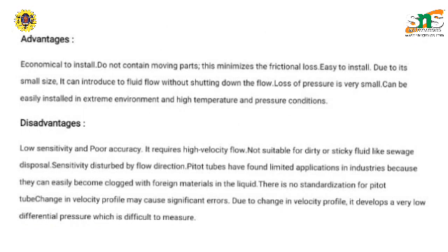Pitot tubes have found limited applications in industries because they can easily become clogged with foreign materials in the liquid. There is no standardization for Pitot tubes. A change in velocity profile may cause significant errors. Due to a change in velocity profile, it develops a very low differential pressure which is difficult to measure.